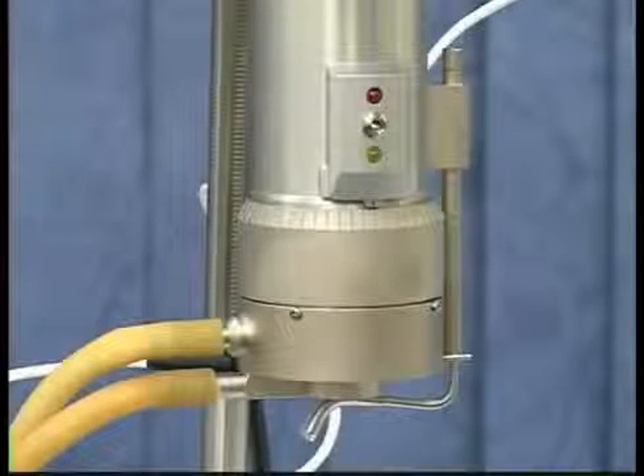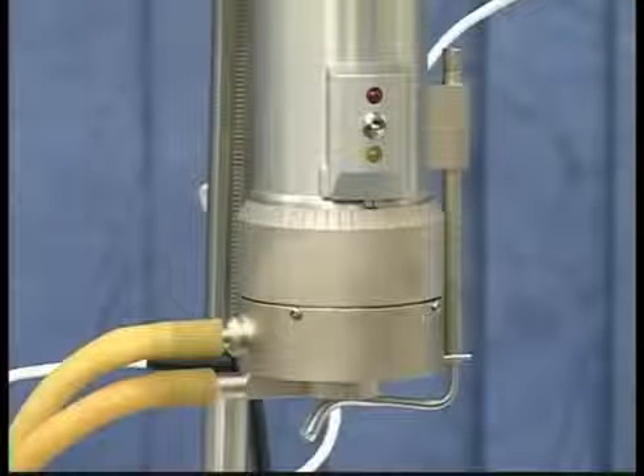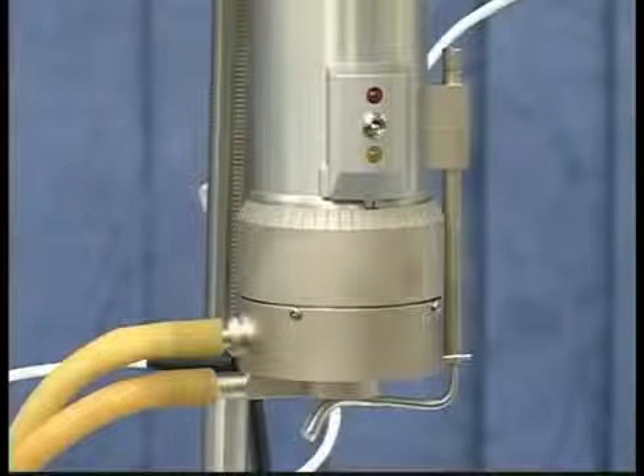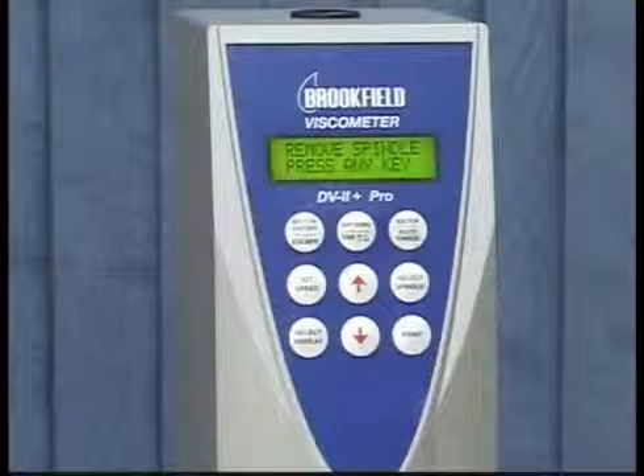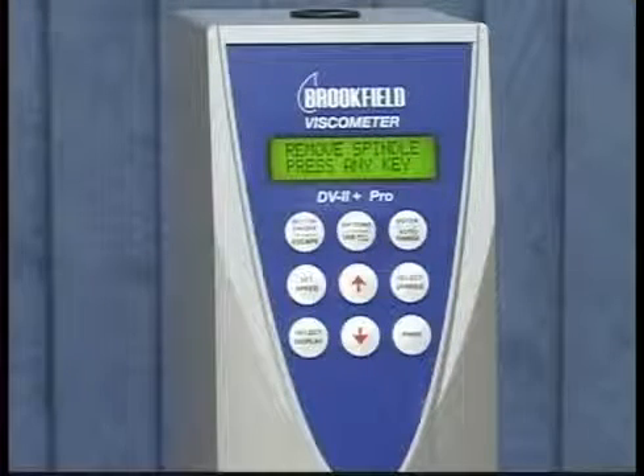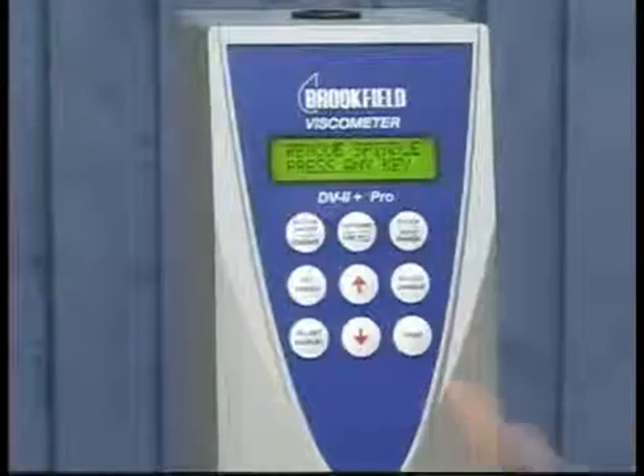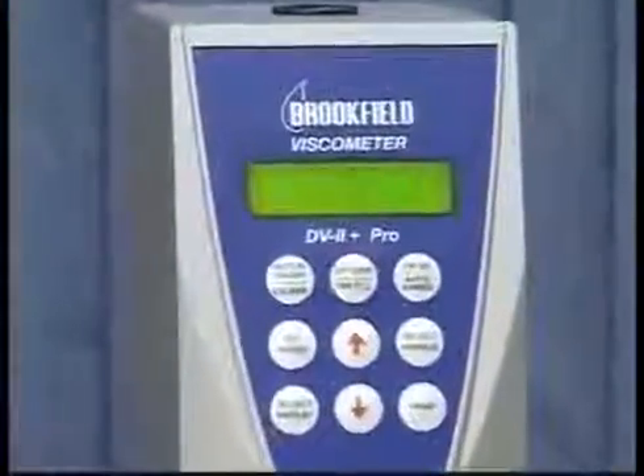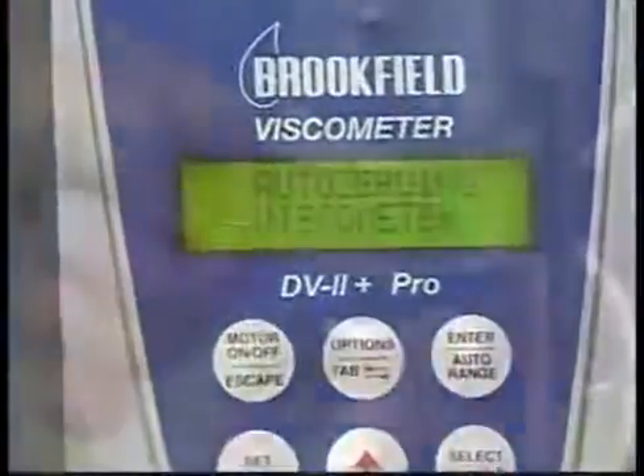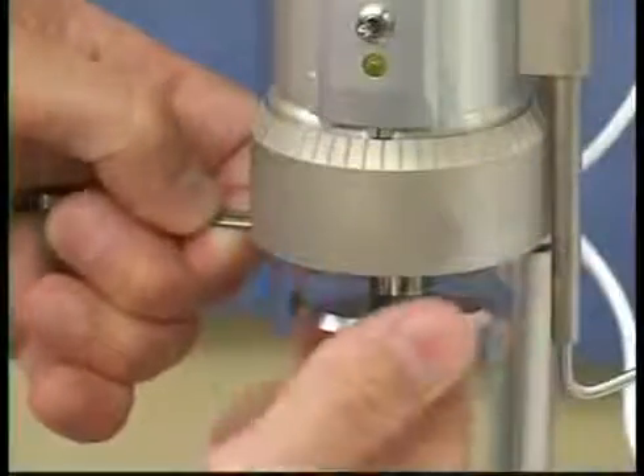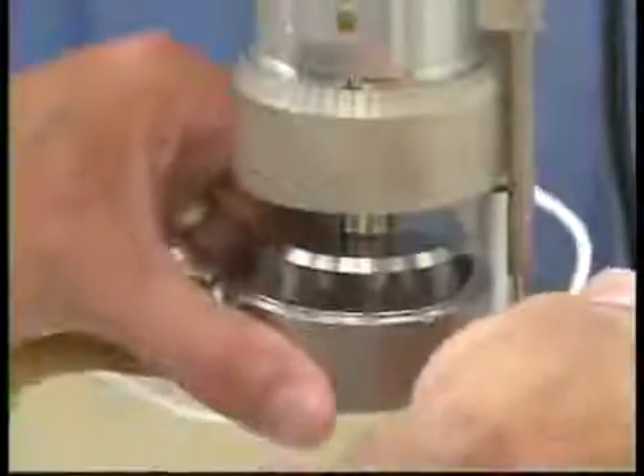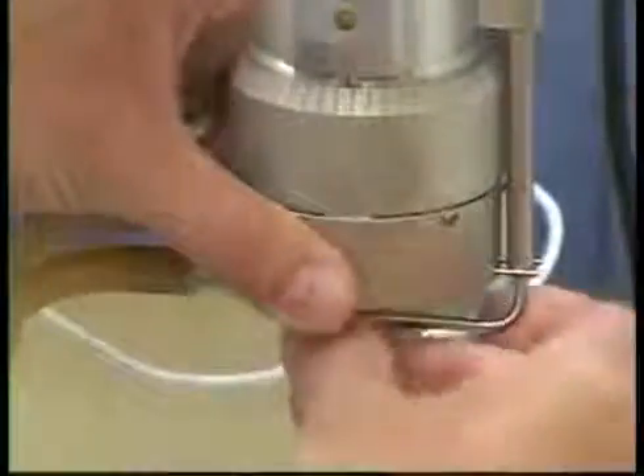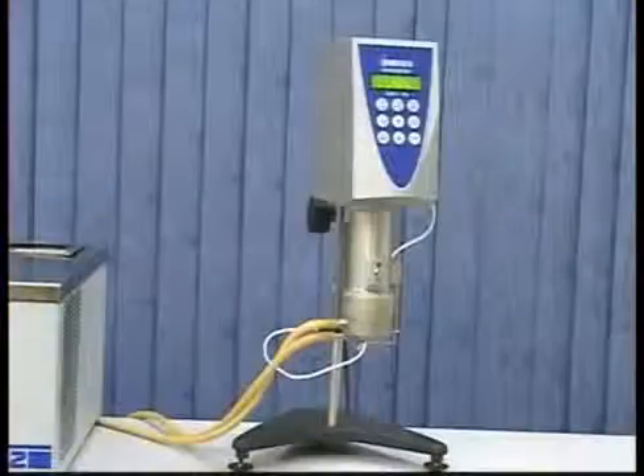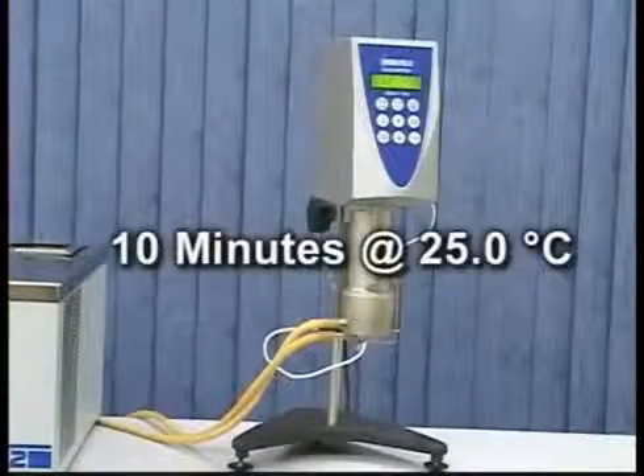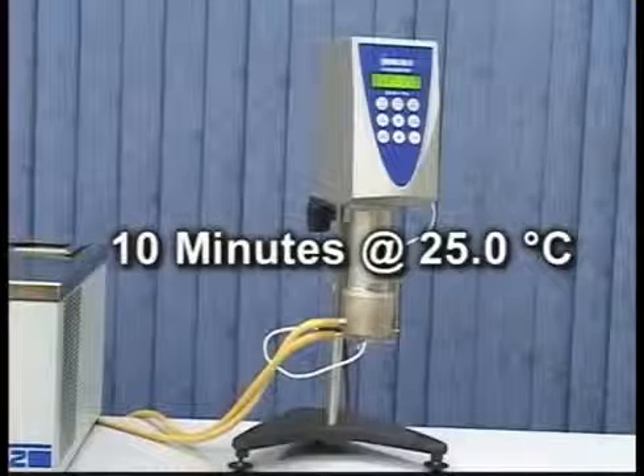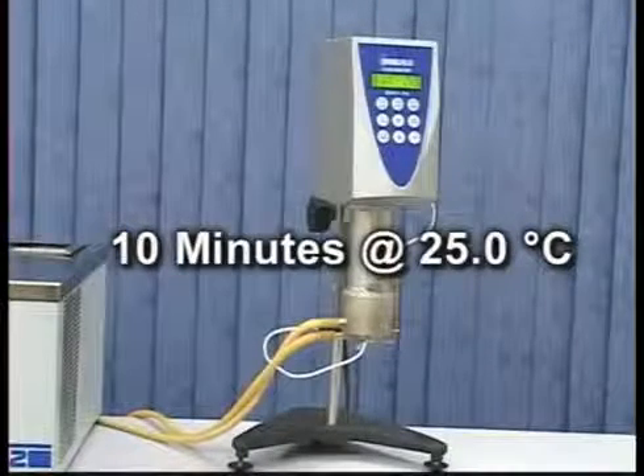One of the most critical aspects to ensure accurate measurements with a cone plate geometry is properly setting the gap. The first step is auto-zeroing the instrument. Turn the instrument on and you will be prompted to remove spindle and press any key. Once the auto-zero is completed, attach the spindle and the cup. To ensure a proper gap setting, allow the cup and spindle to equilibrate for 10 minutes at 25.0 degrees centigrade.